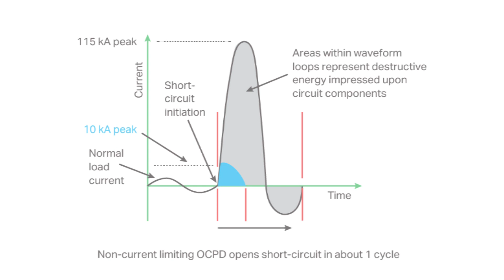The shaded area under the curve represents the energy being dissipated in the circuit, with both magnetic forces and thermal energy being directly proportional to the square of the current, making it important to limit the short circuit current to as small a value as possible. The maximum magnetic forces vary as the square of the peak current, and the thermal energy varies as the square of the RMS current. This waveform demonstrates this same short circuit when the fuse operates within its current limiting range. A current limiting fuse has such a fast response speed that it cuts off the current long before it can build up to its full peak value.